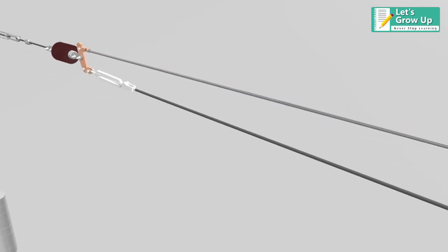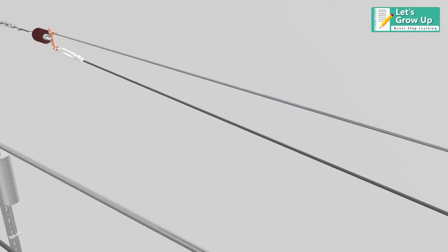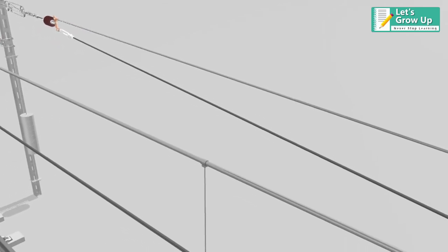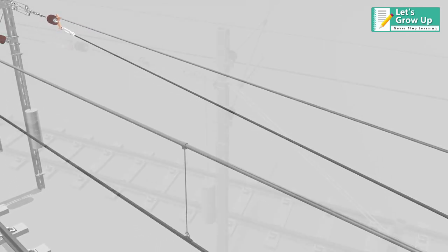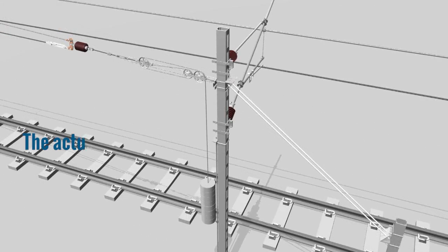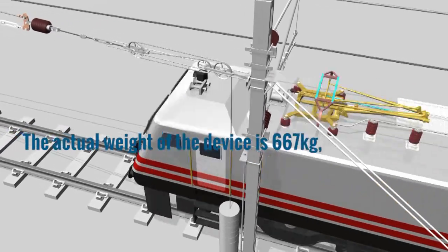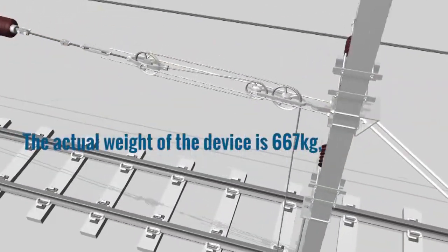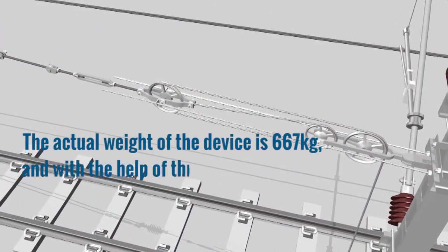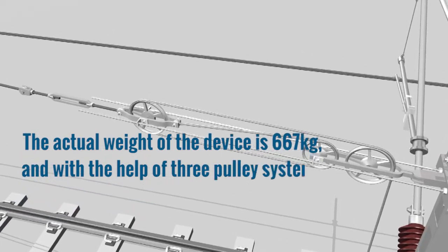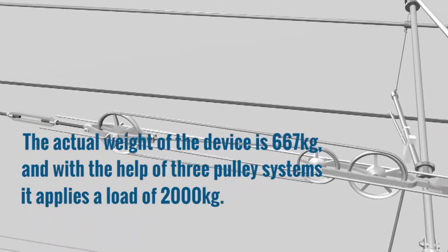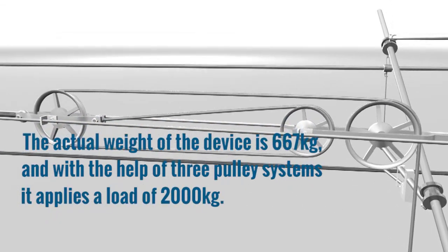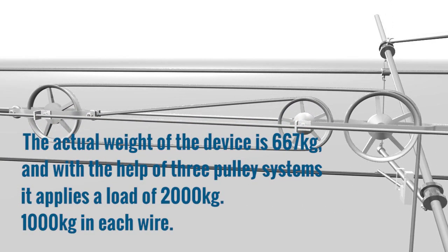A tension of 2000 kg is always maintained on OHE. The actual weight of the device is 667 kg, and with the help of three pulley systems, it applies a load of 2000 kg, 1000 kg in each wire.